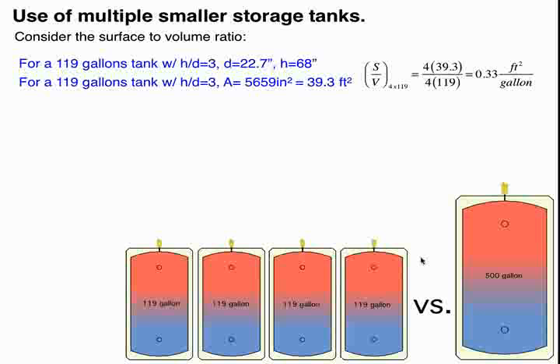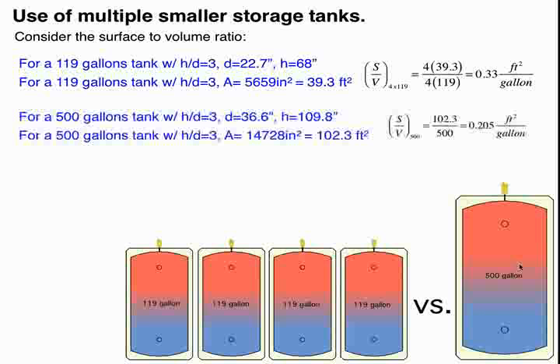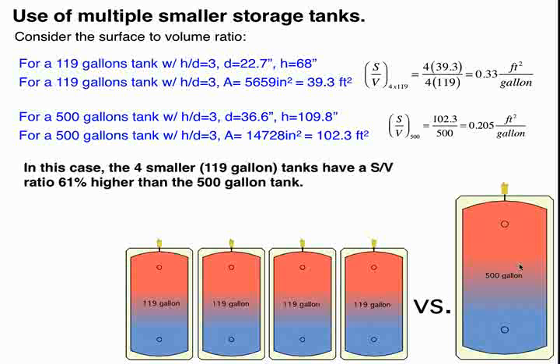So with cylinders, we're going to compare it. And what I did here is I compared 4 tanks at 119 gallons each to a single 500-gallon tank, and I assumed cylinders. Just to keep the math simple, I assumed flat ends. And we calculated a surface to volume ratio. As a quick comparison, the 4 smaller tanks here have a surface to volume ratio that's about 61% higher than the 500-gallon tank. So when would you use the smaller tanks versus the larger tank?